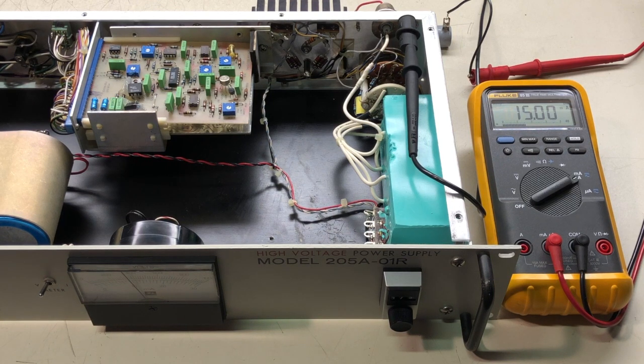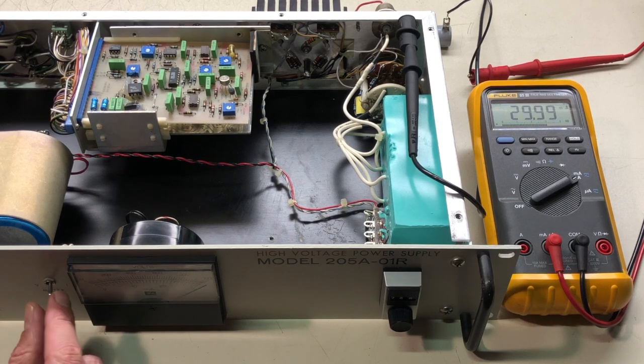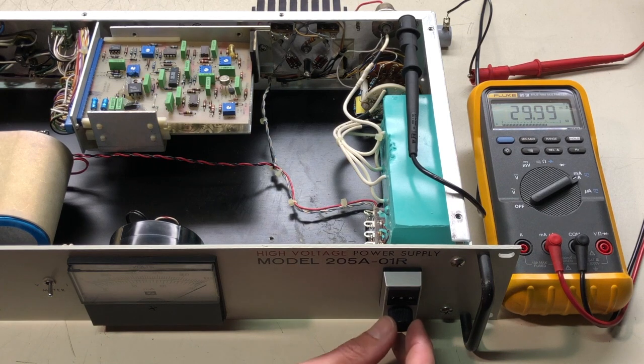Okay, now we're going to increase the voltage so that we get a 30 milliamp current draw. So I'll begin increasing the voltage. There we have it. That looks really good there. 30 milliamps. Very close right there. You can see on the meter over here, 30 milliamps. There's 750 volts, I believe was our, yep, 750, and that looks really close. It maybe is a touch high on the voltage, but the milliamps does read slightly high on this meter. Maybe reading a bit high if I come down. Let's see, yeah, 29. So very, very close on the analog meter on the front.